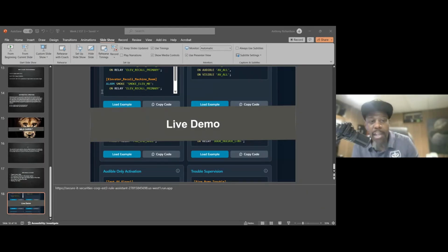We're going to turn that level speaker on. Pretty much we're going to turn all of the speakers on in this entire building. We're going to turn the messages on. So once we turn the amp on, once we turn the speakers on, now we turn the messages on so that way the message can go through the speakers. These are the pre-recorded messages like alarm, go to the stairwell, this is just an emergency, this is not an emergency, or get out of the building. Whatever the message is, you could pre-record that inside the audio.